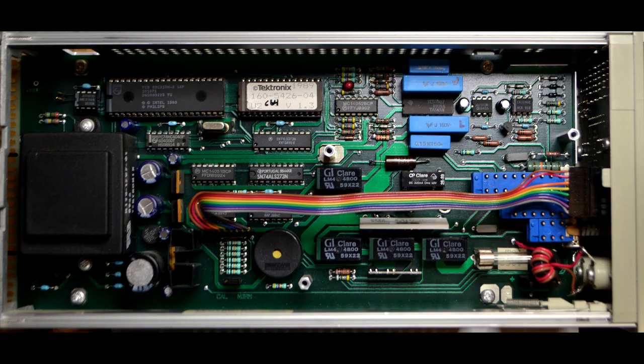The DM504A is self-calibrating. When a jumper is set to CAL mode, the firmware enters a sequence where it prompts the user to apply a series of accurately known voltages, currents, and resistances. For each one, it calculates a factor needed to make the display read the correct value and stores the factor in a 16x64-bit EEPROM. In normal mode, it reads the appropriate constant from the EEPROM for the particular range and function and scales the output of the A to D converter to display an accurate reading.